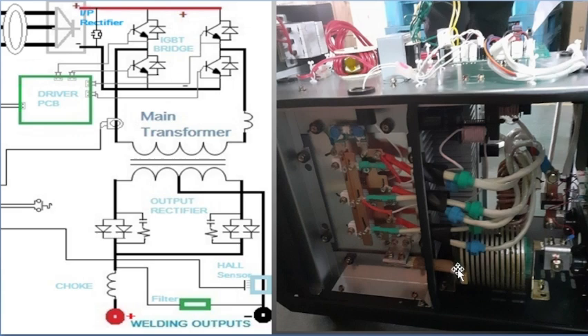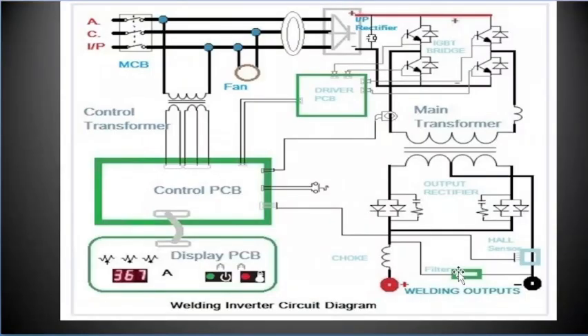So depending on the operation selection, the control PCB sends a PWM high frequency signal in the order of 20 kHz to the IGBT driver PCB. The driver PCB accordingly drives the IGBT gates. The IGBTs switch the DC bus voltage to the primary of the main transformer.